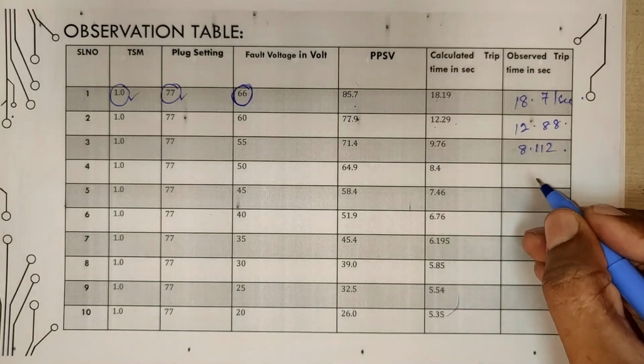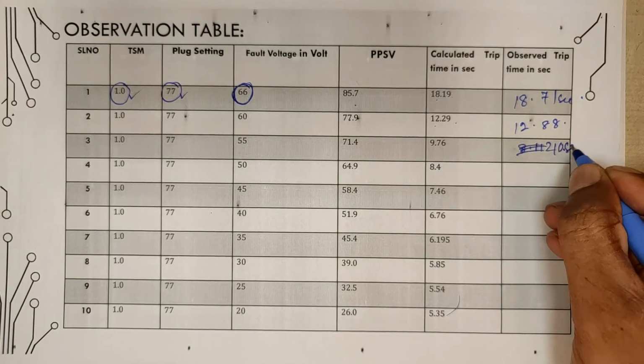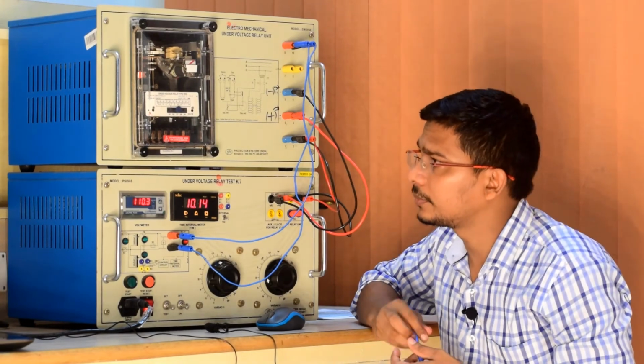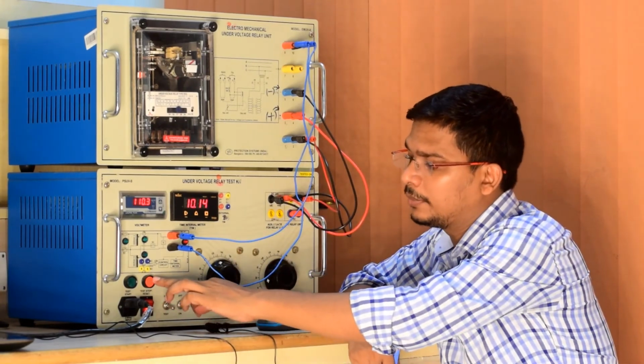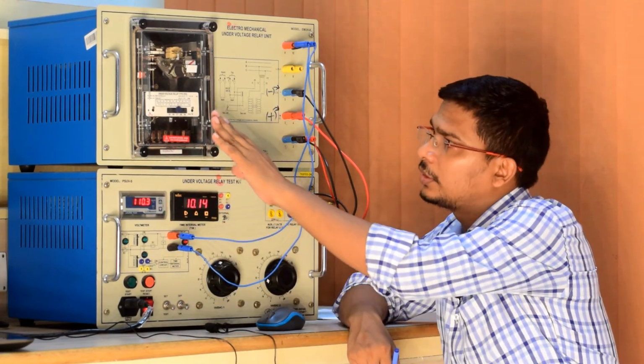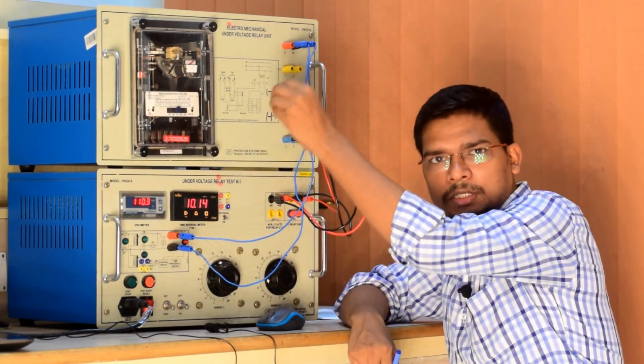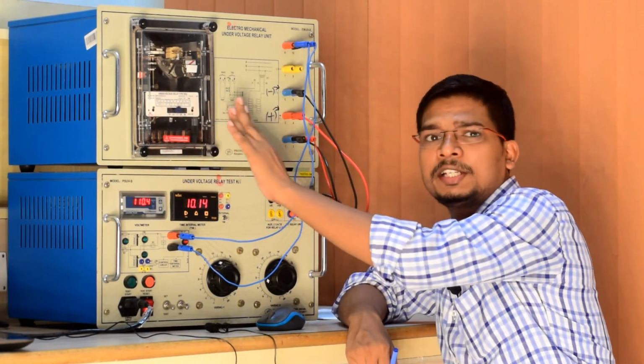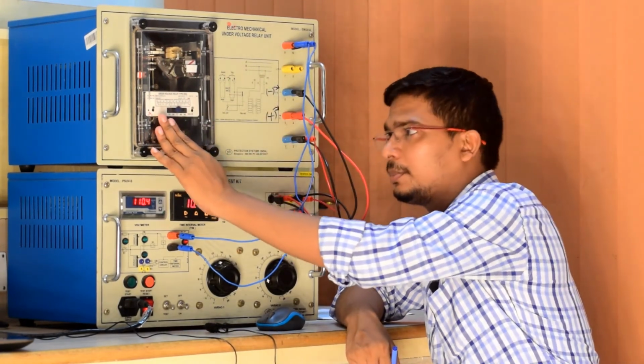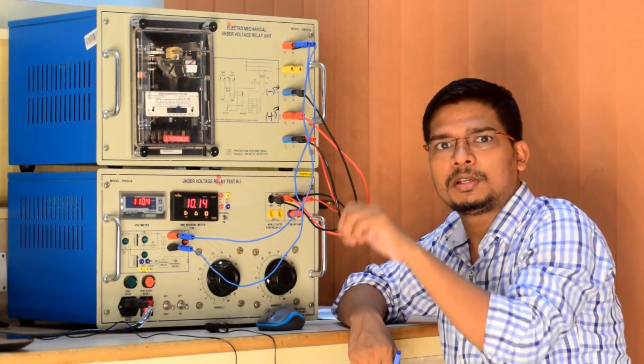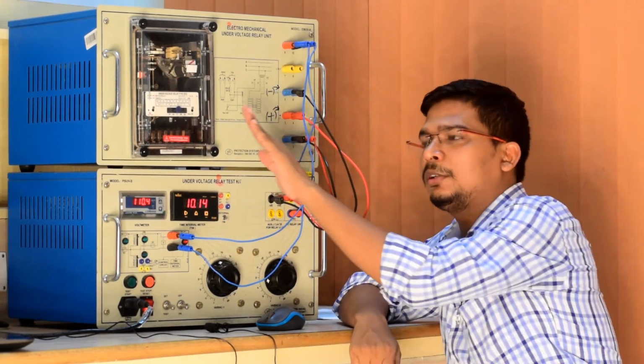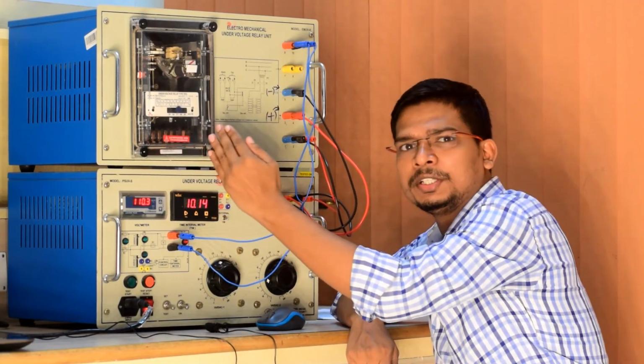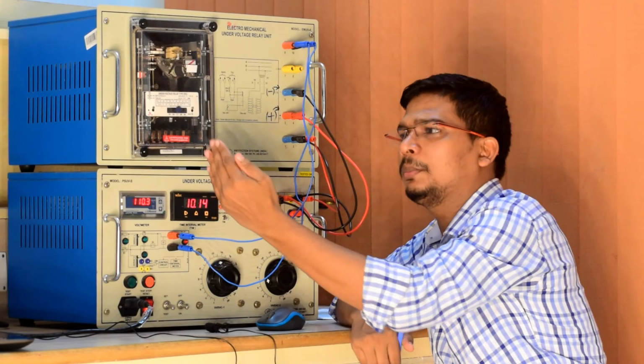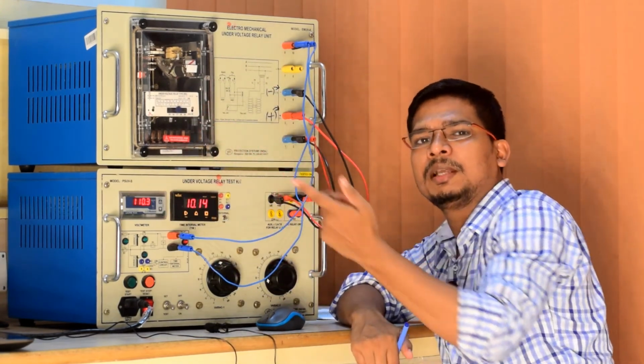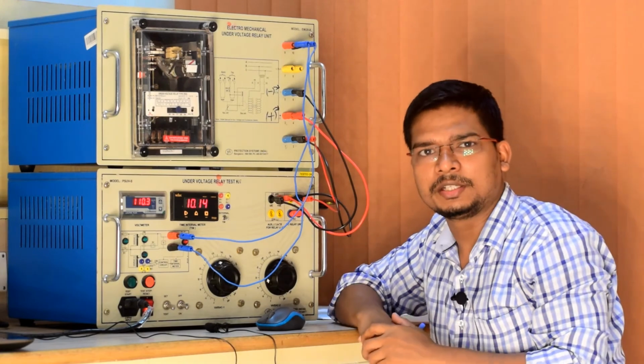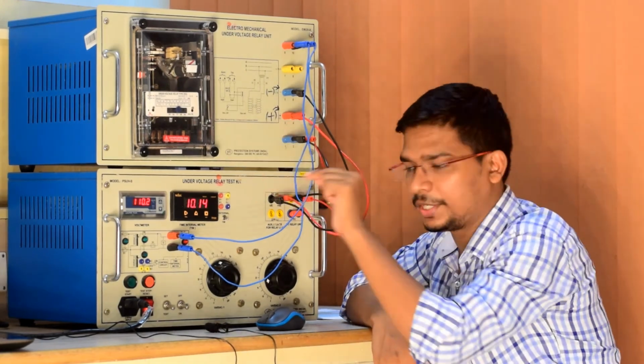Our expectation is 9.76 seconds, 10 seconds. So why did that 2 come? There is a question. Whenever I go for the next observation, the relay, which was earlier in trip mode, should go back to its normal operating mode, and it will take some time. You have to wait. If you do not wait, it will still be moving towards the normal operating position, and during that we apply another voltage. Then from the middle it will come to the trip position, and the time will be less than desired. So right now we have to wait.